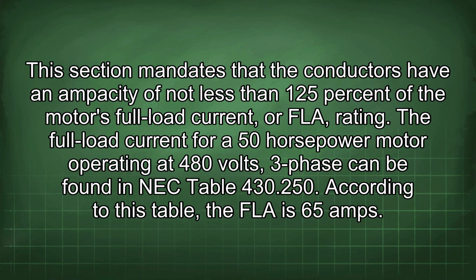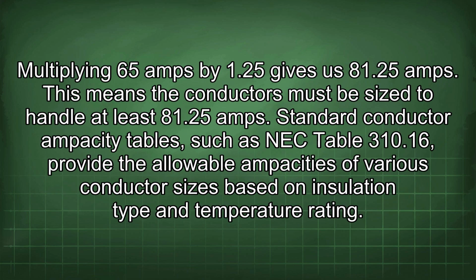This section mandates that the conductors have an ampacity of not less than 125% of the motor's full load current or FLA rating. The full load current for a 50 horsepower motor operating at 480 volts, 3-phase, can be found in NEC table 430.250. According to this table, the FLA is 65 amps. Multiplying 65 amps by 1.25 gives us 81.25 amps. This means the conductors must be sized to handle at least 81.25 amps.